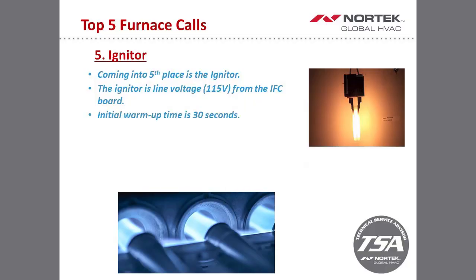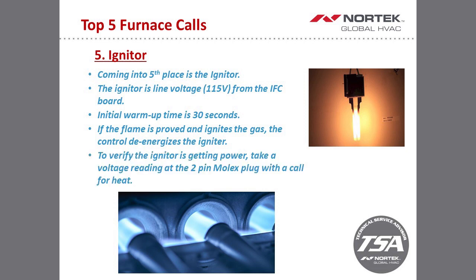The warm-up on the igniter initially is going to be a 30-second warm-up. Then once the flame is proven, the igniter will de-energize in the furnace startup sequence. Now, the igniter will have 2 black wires going to it from the main control board, carrying 115, 120 volts to the igniter. That will de-energize once the furnace is up and running. Also, you want to make sure that the igniter is getting at least 90 volts, because that's what they're tested down to. If you're getting less than 90 volts, then we've got a line voltage problem, and we may need to address something in the electrical panel.